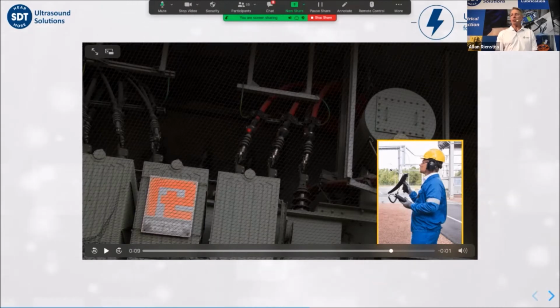So we know there's corona or partial discharge activity on one of these three phases. By using his laser sight from a safe distance away, we're enabled to pinpoint exactly which one is the troublemaker.